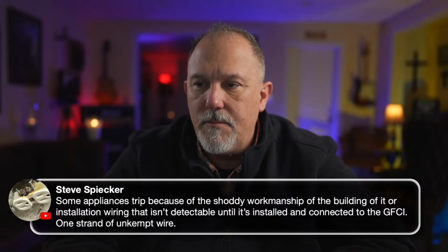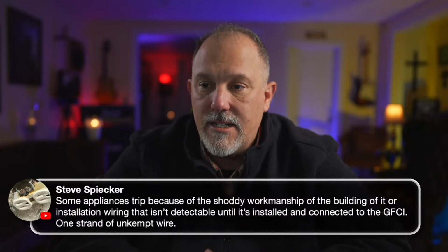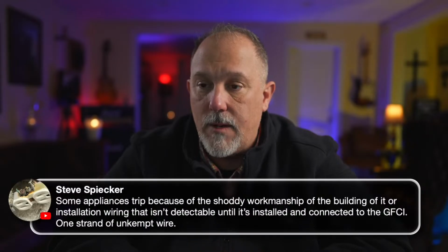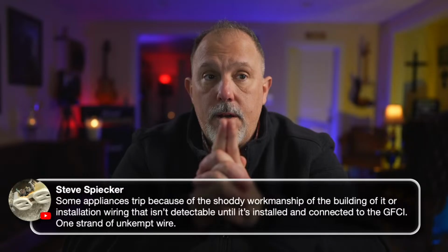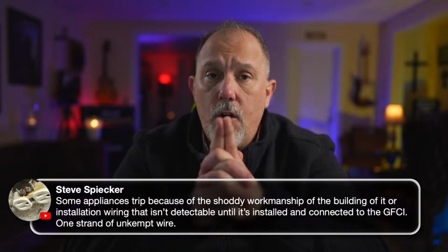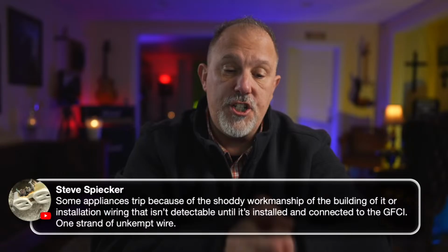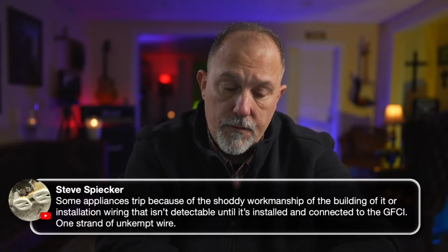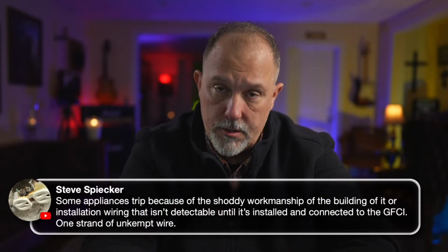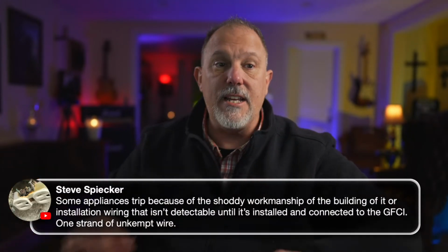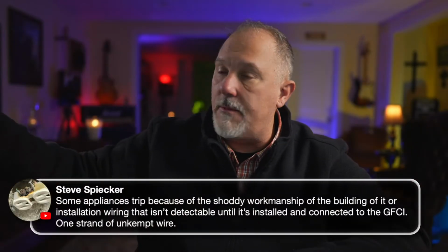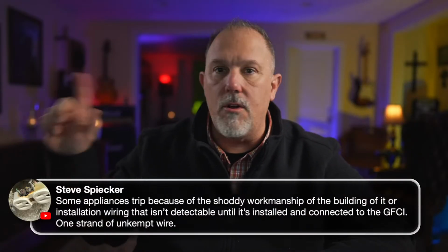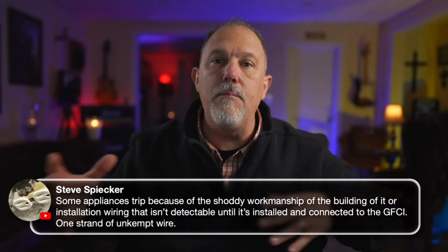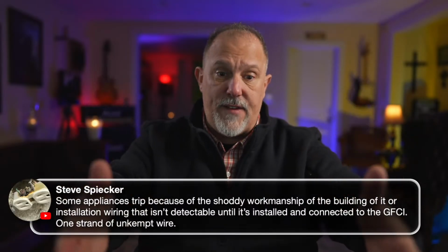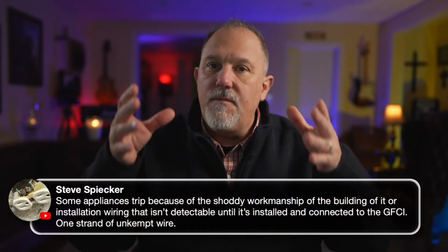Tesla is something else. Steve, some appliances trip because of the shoddy workmanship of the building of it or installation wiring that isn't detectable until it's installed and connected to the GFCI, one strand of unkempt wire. Steve, I would say here's the other issue. We saw this in the change in Article 422 for vending machines. They put a GFCI requirement in 422.5 for a vending machine in the cord. They changed the standard because vending machines get moved from place to place. You throw them on a truck, you take them off the truck, you set them here. When someone says, I'm going to move that over to this store because that guy's no longer going to pay rent, you put it on a truck and you put it over there. In that moving, it is not necessarily that the manufacturer of the vending machine did a shoddy job. It's the fact that you've been moving it, and you can't even blame it on the movers.